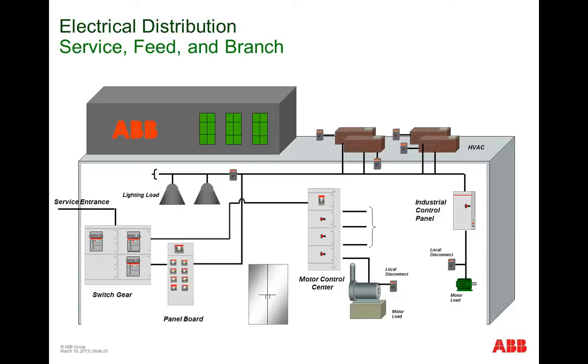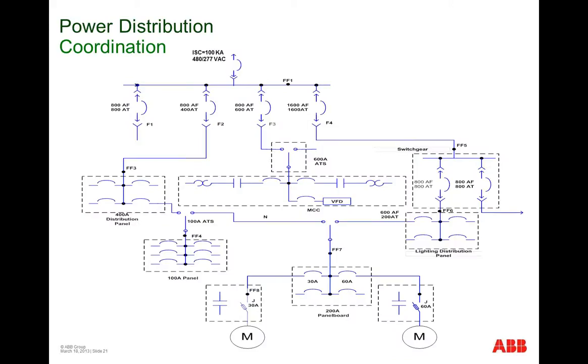Electricity comes into a factory or a commercial building at what's known as a service entrance, shown on the left here. Switchgear is used to provide a means of disconnecting the power, but also protecting the facility from major faults, such as a short circuit. Frequently, there's a transformer that steps the voltage down to a panel board or a motor control center, shown in the center here. These panels have additional circuit protection on smaller circuits for loads such as lighting loads, heating and air conditioning equipment, maybe even plant floor machinery.